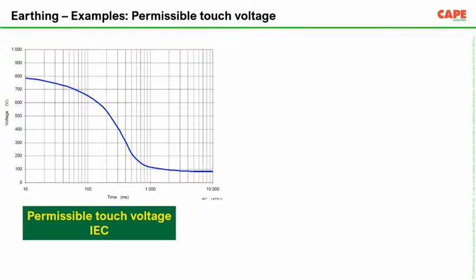So the earthing system, say for example bonding, interconnection of different items in a substation. The bonding shall be made in such a way that the lead length is as minimum as possible. As a result, the touch voltages during a fault are limited. Yes, absolutely correct.